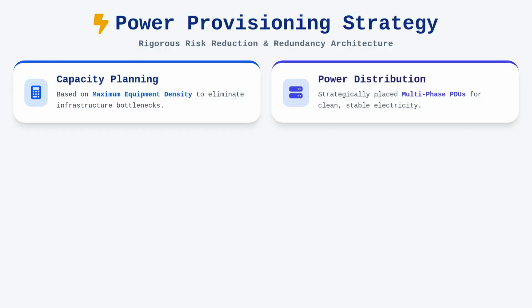Power provisioning follows the same philosophy of rigorous risk reduction and redundancy. Every piece of equipment in the room relies on stable, clean electricity, which requires robust multi-phase power distribution units distributed strategically throughout the racks. We must calculate the total heat dissipation and power consumption based on the maximum equipment density rather than current usage to ensure the infrastructure does not become a bottleneck. An uninterruptible power supply system must be integrated to bridge the gap during utility power transitions, with battery strings sized appropriately for the load duration requirements.